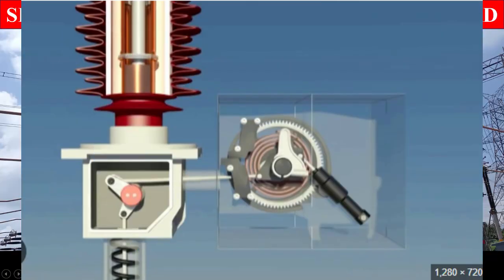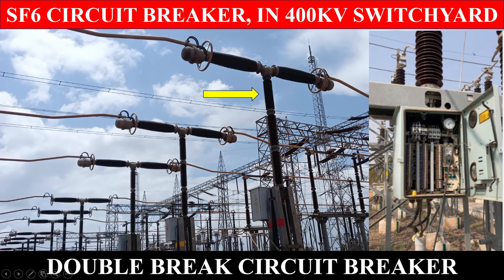Working principle. In the closed position of the breaker, the contacts remain surrounded by SF6 gas at a pressure of about 2.8 kg/cm². When the breaker operates, the moving contact is pulled apart and an arc is struck between the contacts. The movement of the moving contact is synchronized with the opening of a valve which permits SF6 gas at 14 kilograms per square centimeter pressure from the reservoir to flow to the arc interruption chamber.